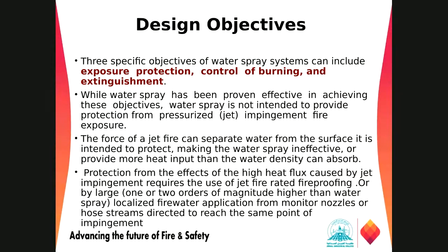Water spray system is very effective in achieving the objectives mentioned by those standards, but a water spray system is not intended to provide protection from pressurized jet impingement fire, right? Pressurized jet impingement fire means that if there is a storage vessel highly pressurized, maybe up to 100, maybe up to 500 psi, and there is a small leakage or rupture in this pipe, due to that small leakage we will get a tremendous amount of flammable vapors outside.